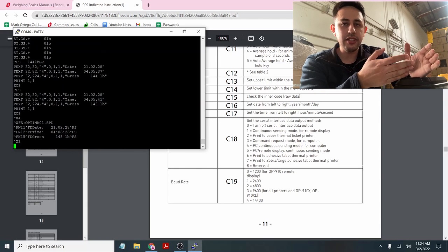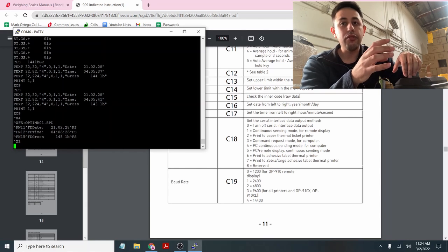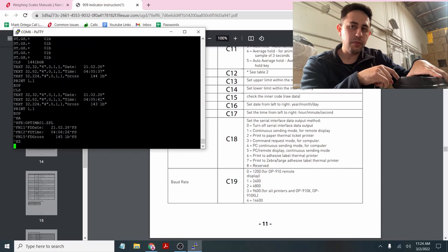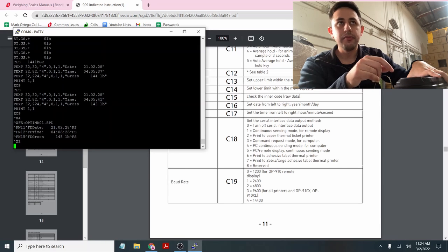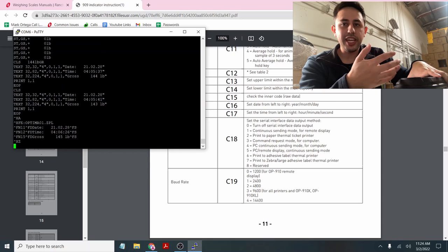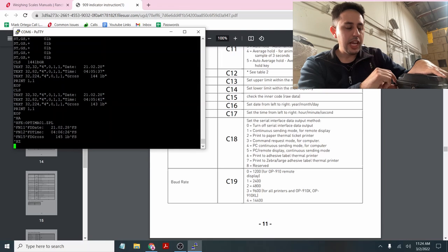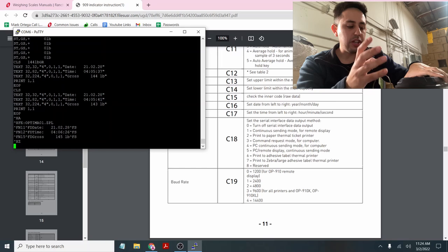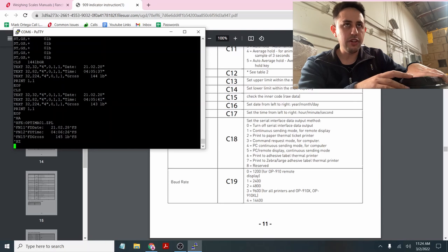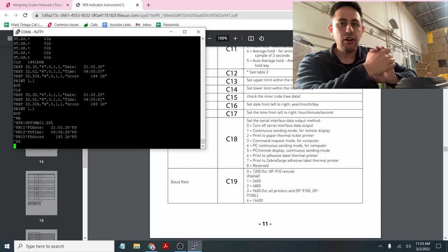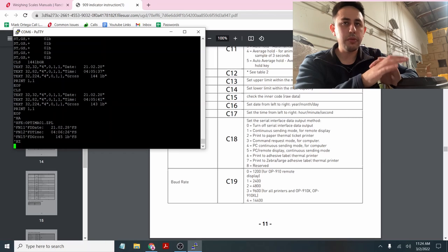If it doesn't read any data, it's not a problem with the software. It's probably because you connected it wrong or are using the wrong setting. So I recommend everyone use C18-4 just to see if you get any output at all. And then once you get output from that, you can start working on the other devices. So then you connect to your printer, scoreboard, whatever you're trying to do. Anyways, that's how you connect the 909 to a computer, printer, or scoreboard using different settings. All right, thank you.